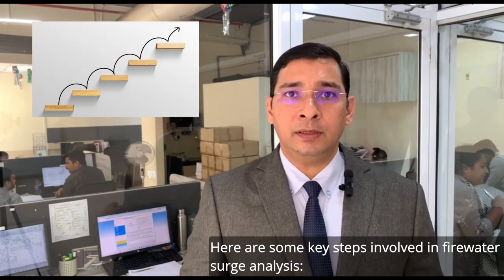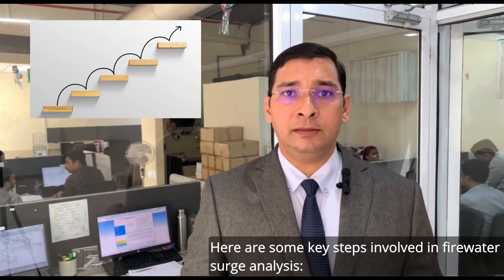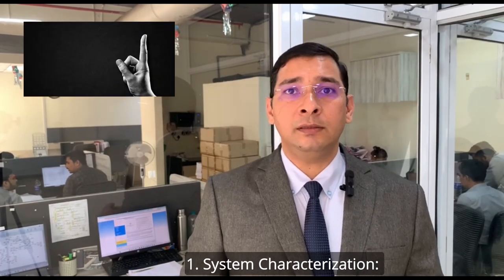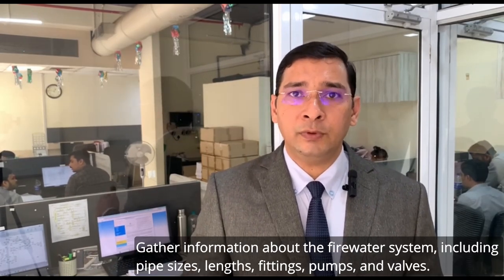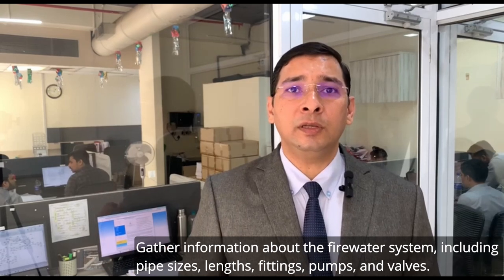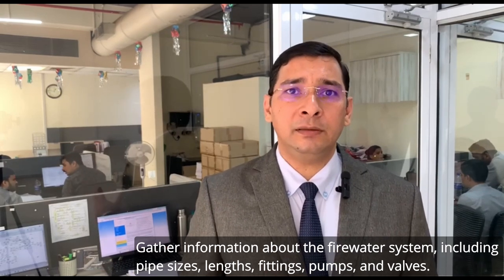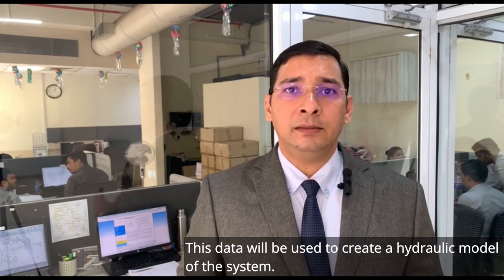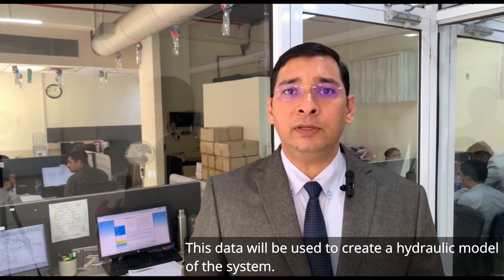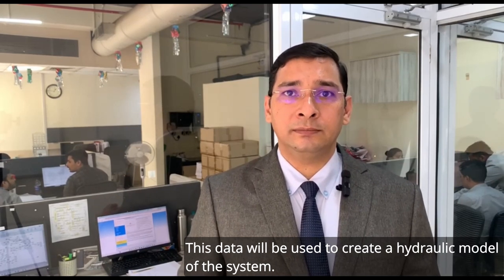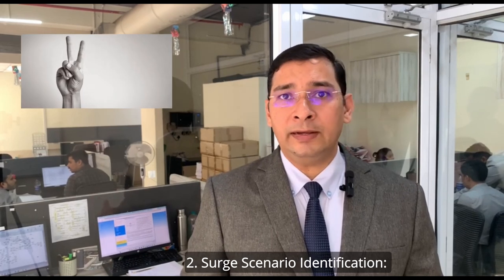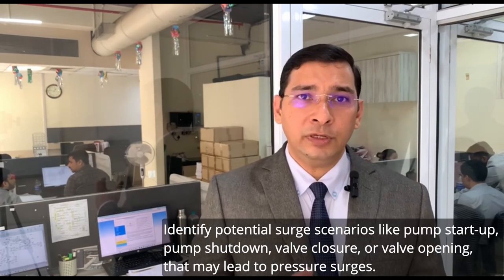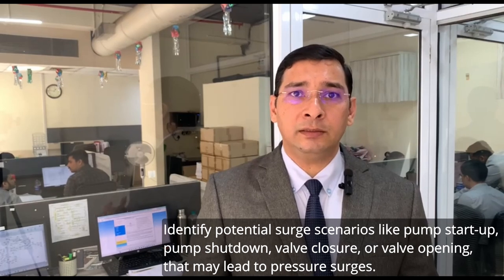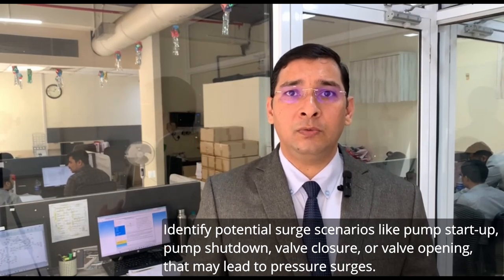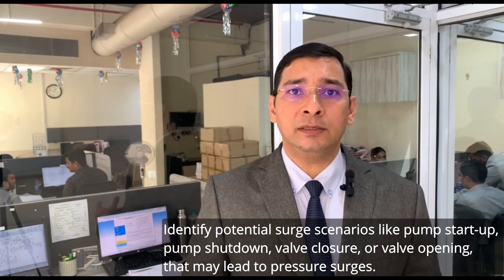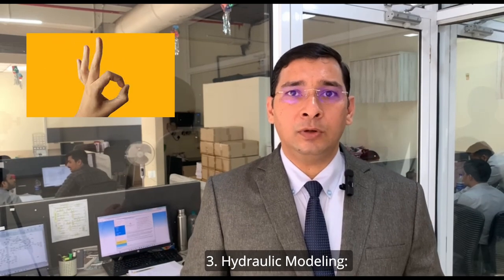Here are some key steps involved in firewater surge analysis. The first one is system characterization. Gather information about the firewater systems, including pipe sizes, lengths, fittings, pumps, and valves. This data would be used to create a hydraulic model of the system. Second, surge scenario identification. Identify potential surge scenarios like pump startup, pump shutdown, valve closure, or valve opening that may lead to pressure surges. Third step is the hydraulic modeling.